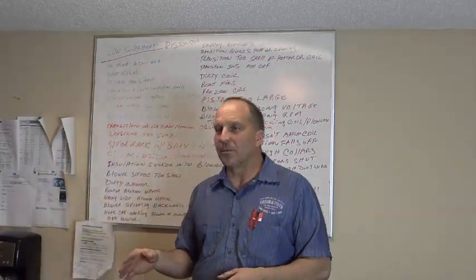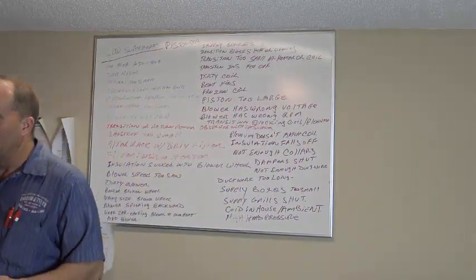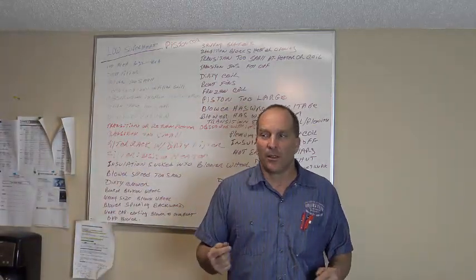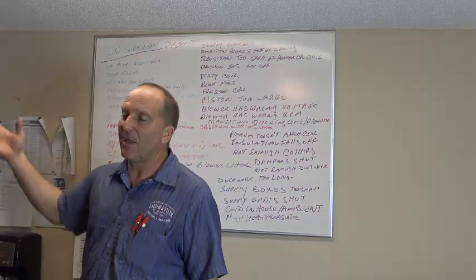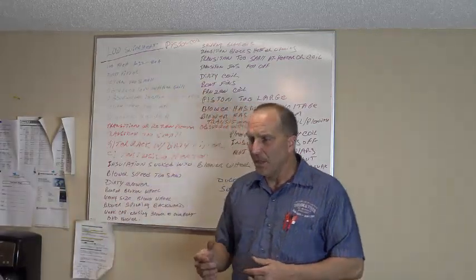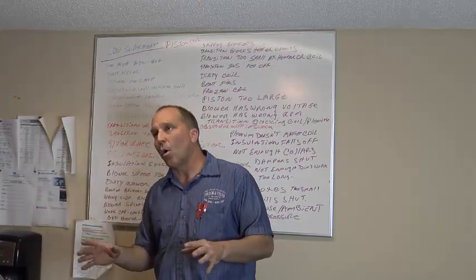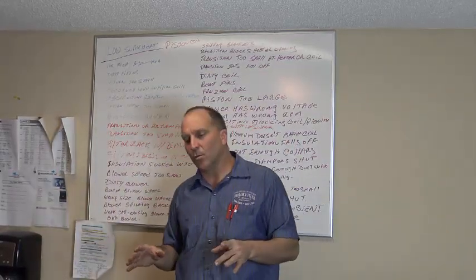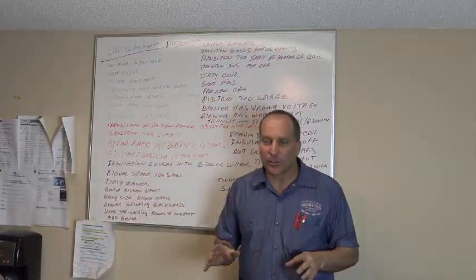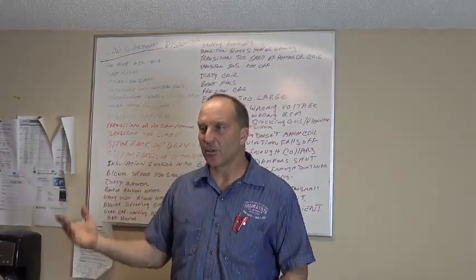Now your return air is going to run a negative 0.3 static pressure, and your supply air by itself would run a positive 0.2 static pressure. Therefore, the two combined, positive 2 and negative 3, gives you a 0.5 static pressure on your system. With this being said, all normal air conditioners for residential homes are designed at a 0.5 static pressure overall in the system. And when I say overall in the system, I'm saying your return and your supply.